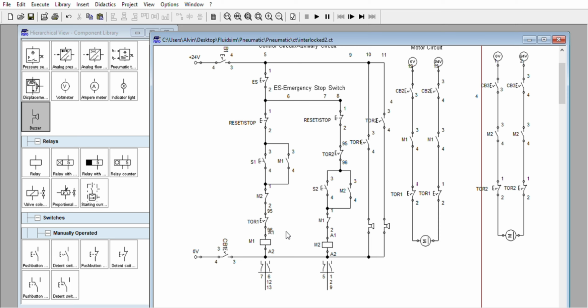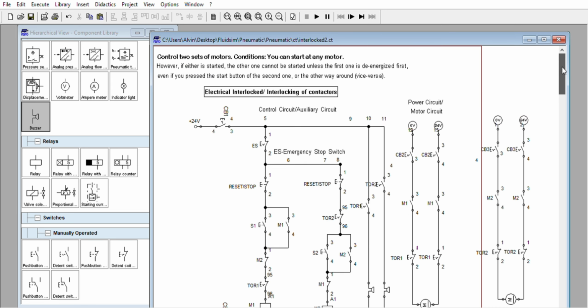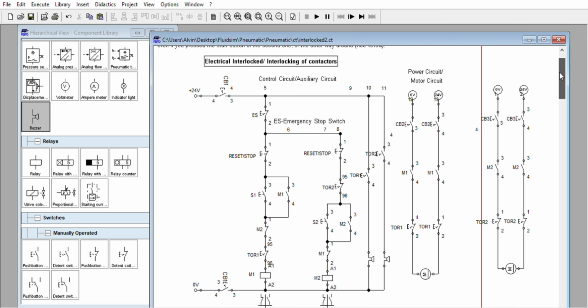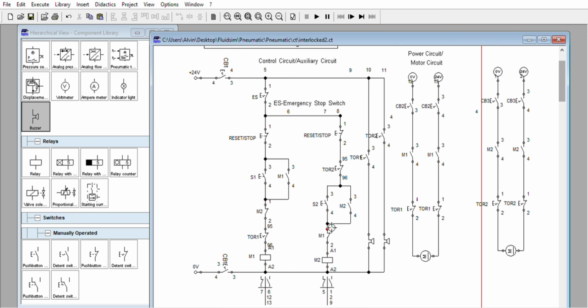Usually the old wirings, they have that one, but newly made wiring, usually electrical interlock. They even have multiple electrical interlock here for maximum safety. You can put 2 M2 here, you can put 2 M3 here, but you will add another auxiliary to your magnetic contactors.